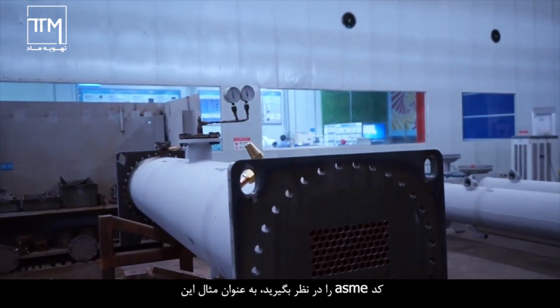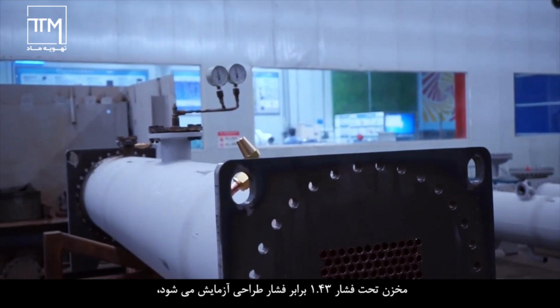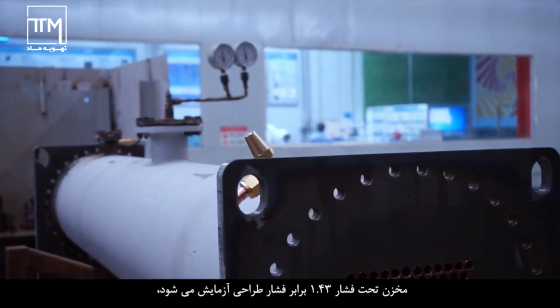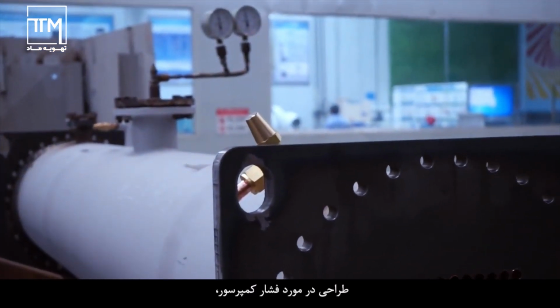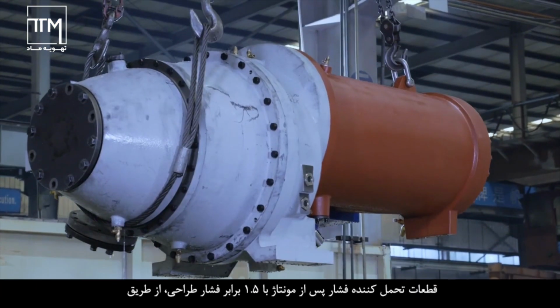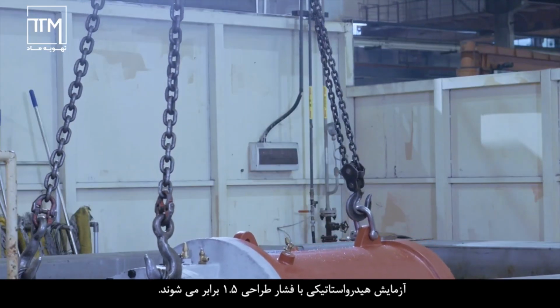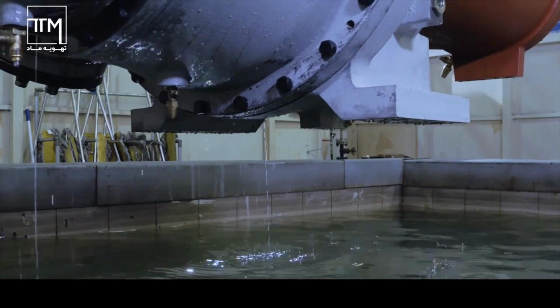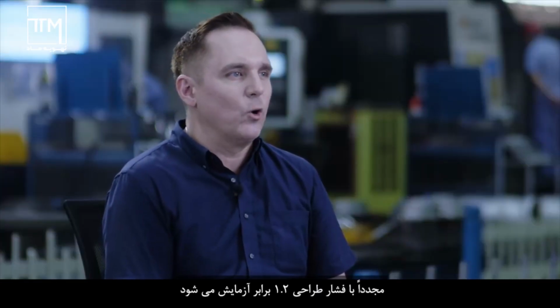Take the ASME code, for example. This vessel will be tested under 1.43 times the design pressure. As for the compressor, the pressure-bearing parts will go through a hydrostatic test with 1.5 times the design pressure. After the assembly, the whole compressor will be tested again with 1.2 times design pressure to ensure its airtightness.